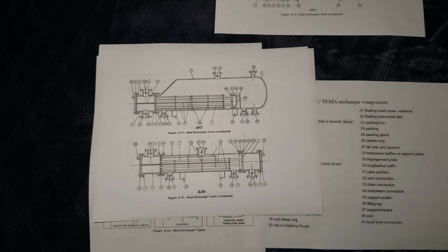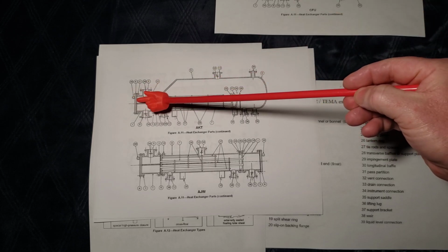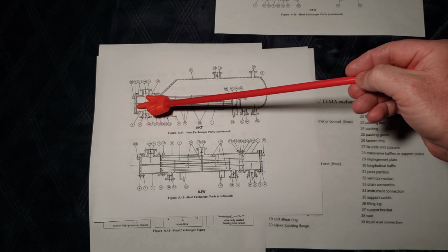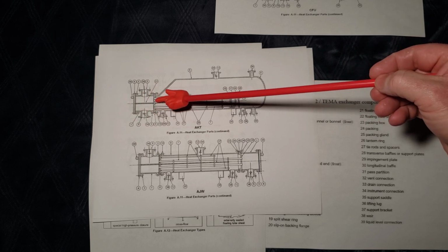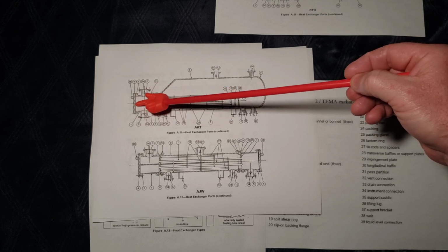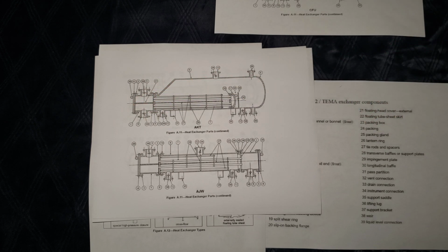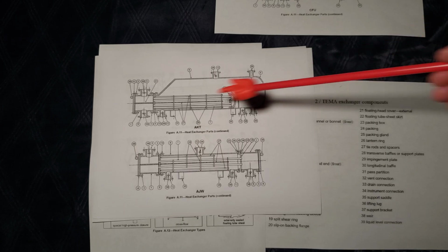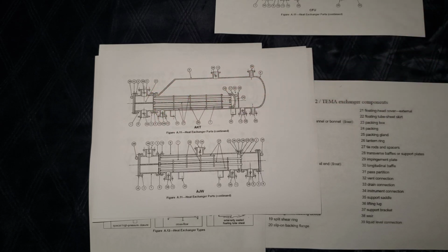That would be important. That way you could work on the tube face for whatever reason at the tube sheet without having to pull the entire gasket or try to roll the gasket onto the backside, which allows you to work on the tube sheet face without having to reach through the channel, which is why a lot of times they will thread the tube sheet. A lot of people don't like it because it makes it harder to stab a bundle, and it gives you the chance of damaging the bolt studs in insertion if the bolt studs are still in place.